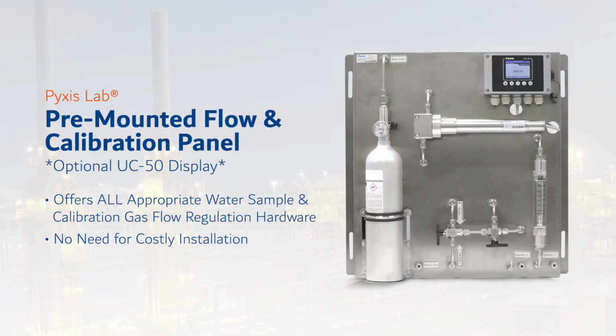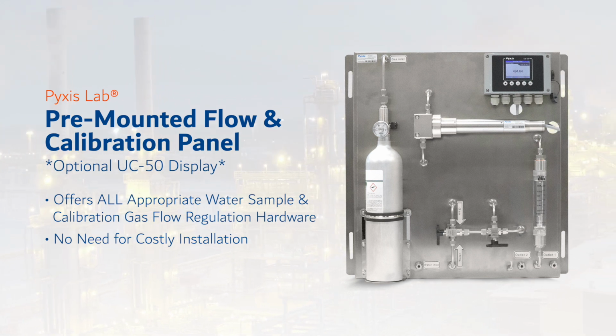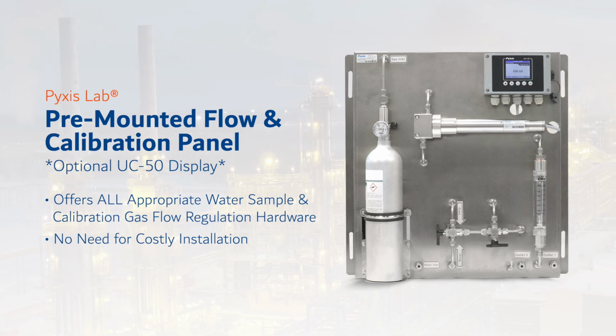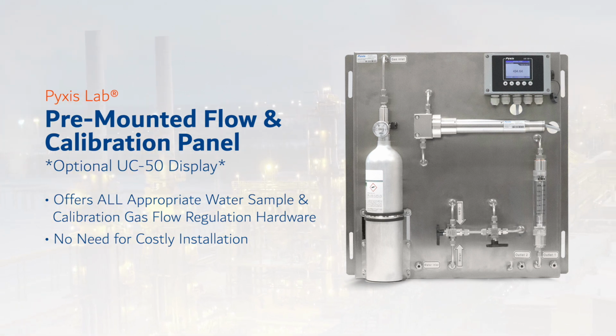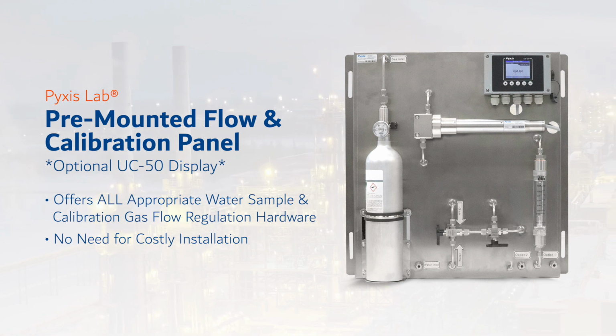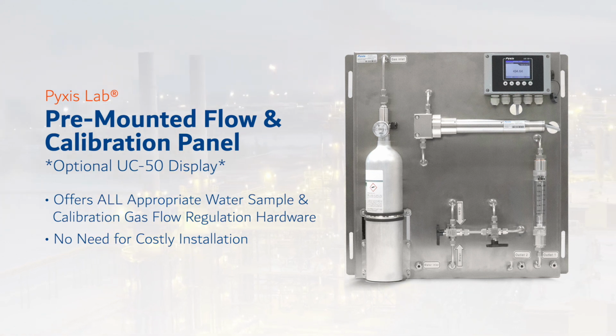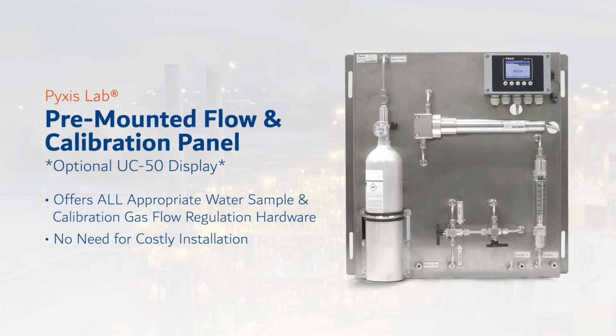For fully integrated turnkey installation, Pyxis Lab offers the ST-774 pre-mounted flow and calibration panel as a pre-assembled and easy-to-integrate solution for users desiring the ST-774 ultra-low DO sensor pre-mounted with a flow cell and all appropriate water sample and calibration gas flow regulation hardware. With a manageable panel size, this system may be used in both permanent installation or portable applications and allows the user to rapidly deploy the ST-774 on a cooled water sample line without the need for costly installation. The ST-774 output wiring allows the user to terminate the pre-mounted sensor to any receiving controller, PLC, or DCS.